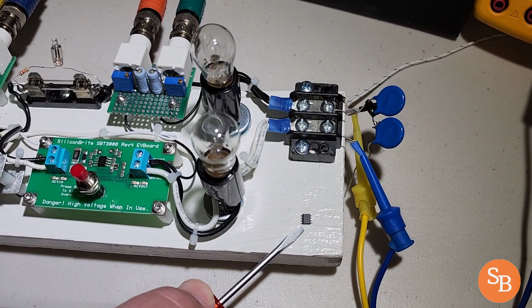First of all, I have a variac which takes the input power, and I can control the voltage. That goes into a step-up transformer, and the reason for the step-up transformer is that with the normal line voltage here, I can't get high enough voltage to trip the SBT3000 to artificially create an overvoltage condition.